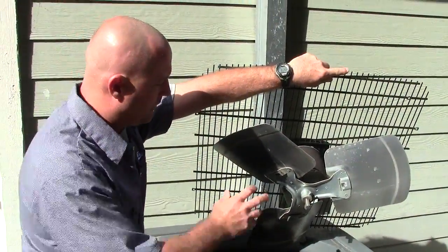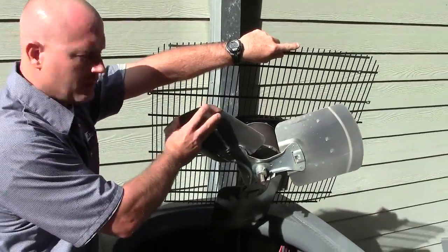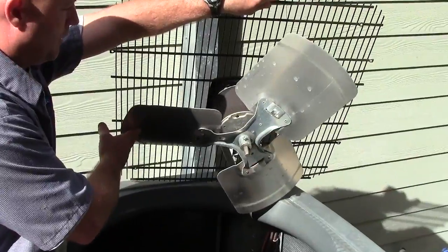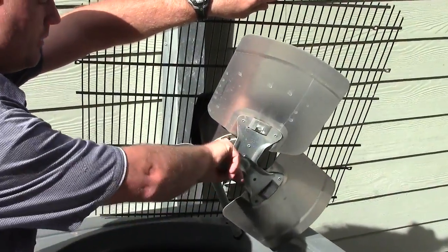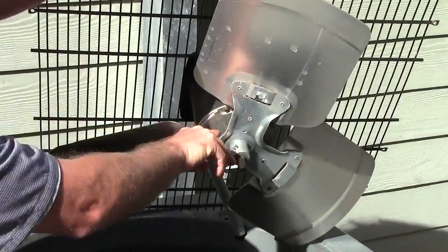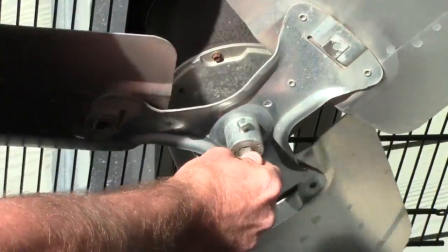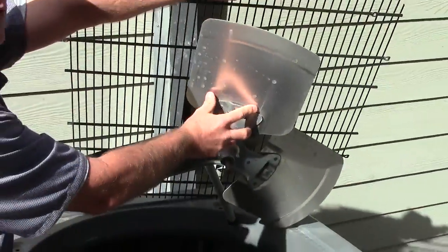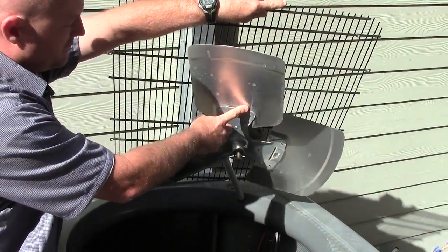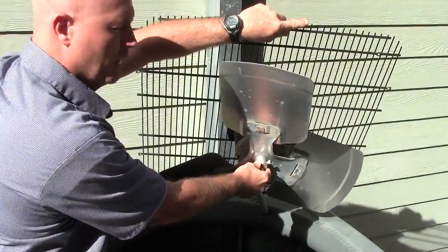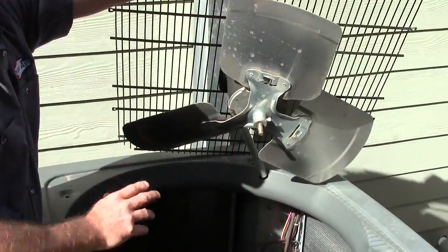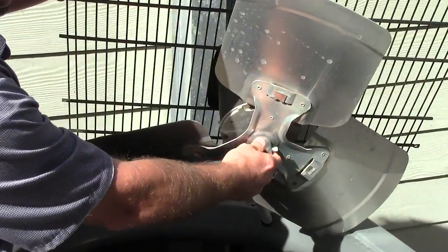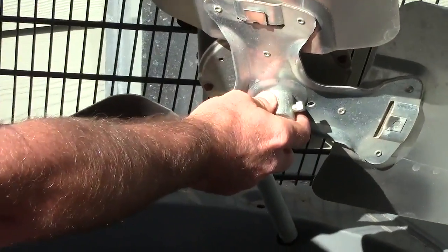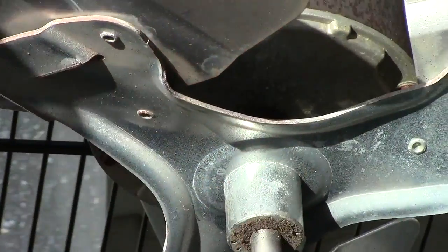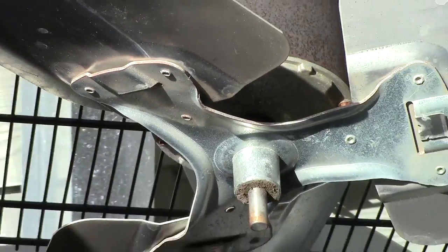This component right here is your fan, your condenser fan motor and blade. What we're looking for here is any oil that's leaking from the sealed bearings around the shaft. Looking at the machine itself, the blades, making sure that none of these are cracked or have hairline cracks in them. They will cause serious issues. We're also checking the thrust bearing and lateral play on the bearings by feeling the shaft, pushing it in and out, and moving it back and forth, making sure everything spins freely without rubbing or making any funny noises.